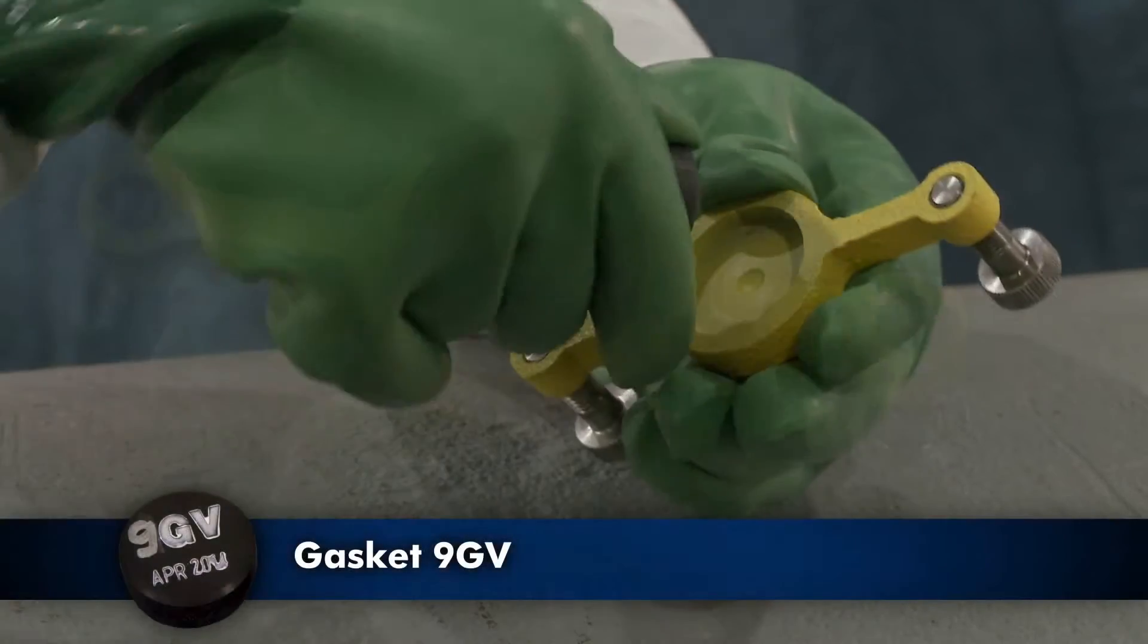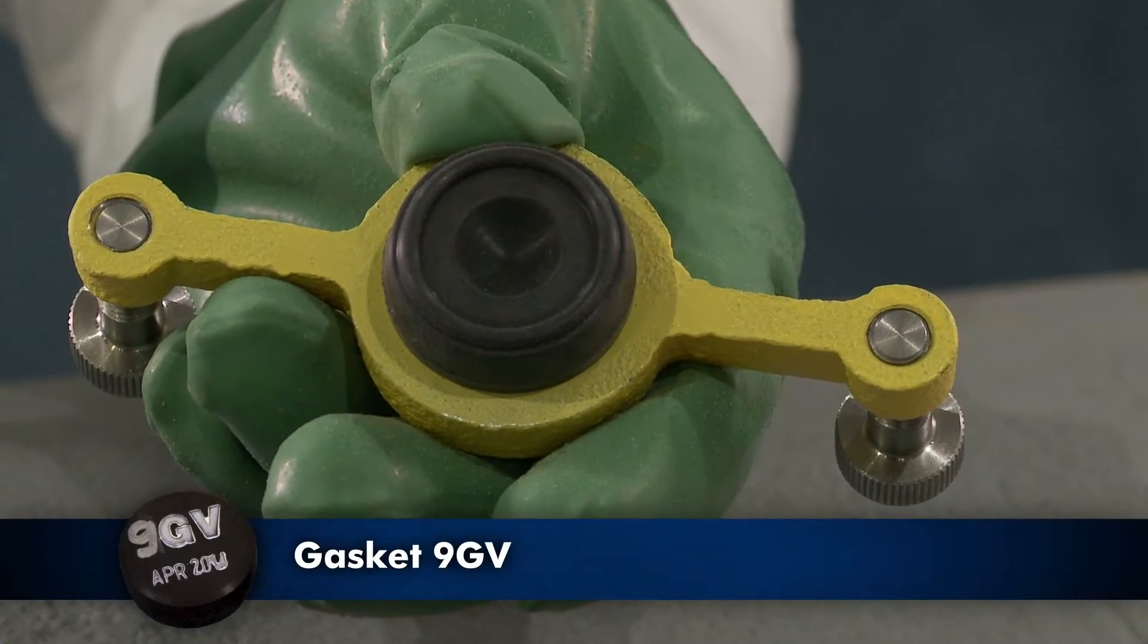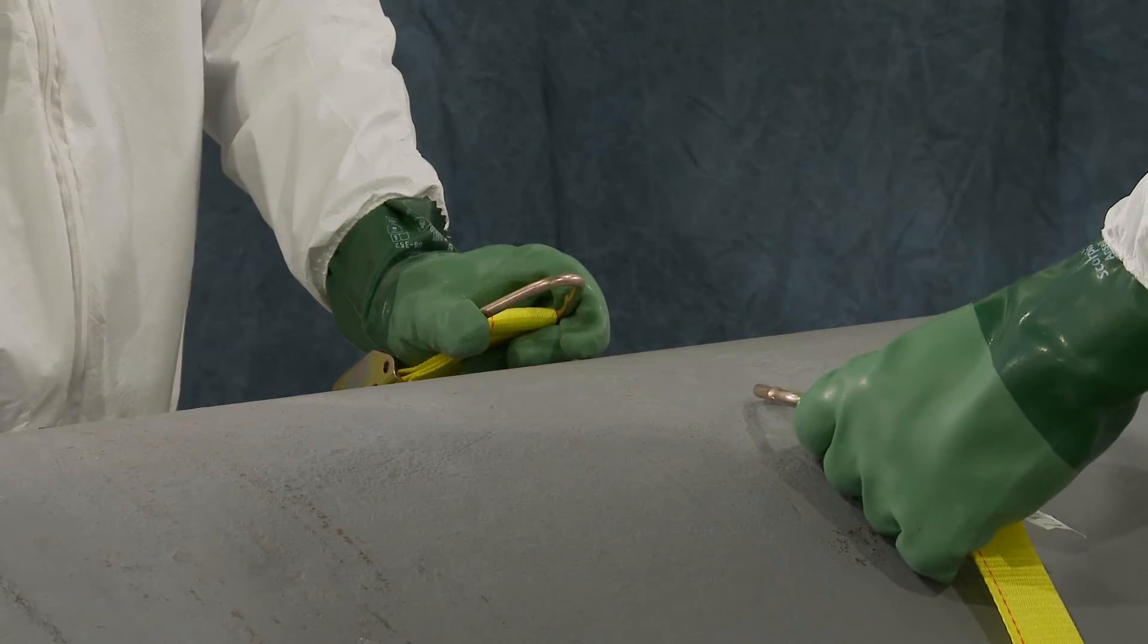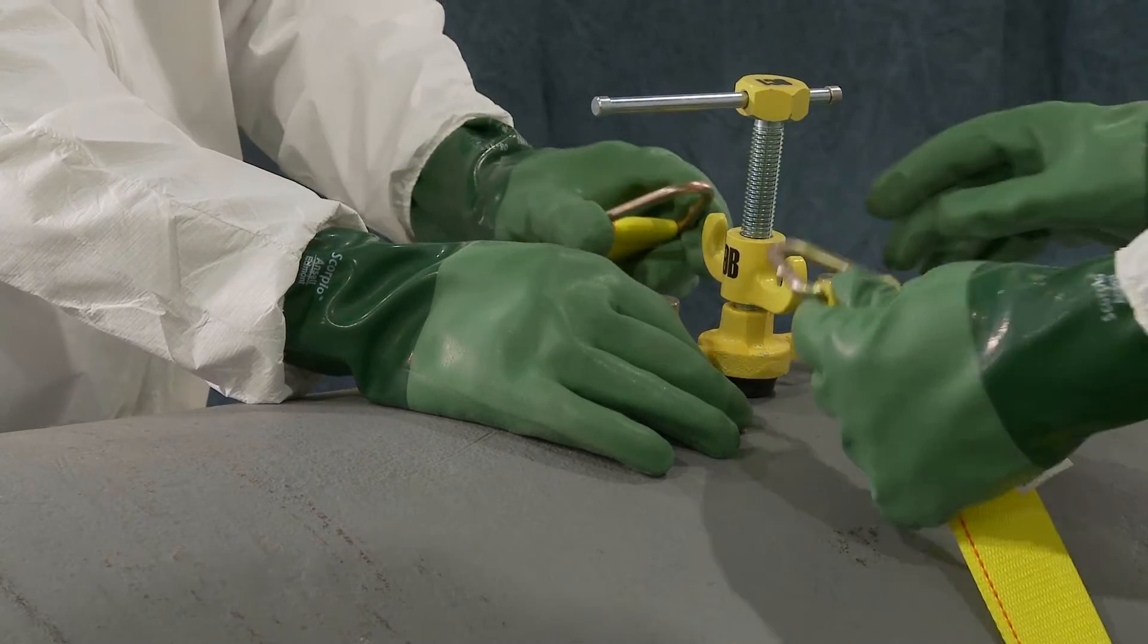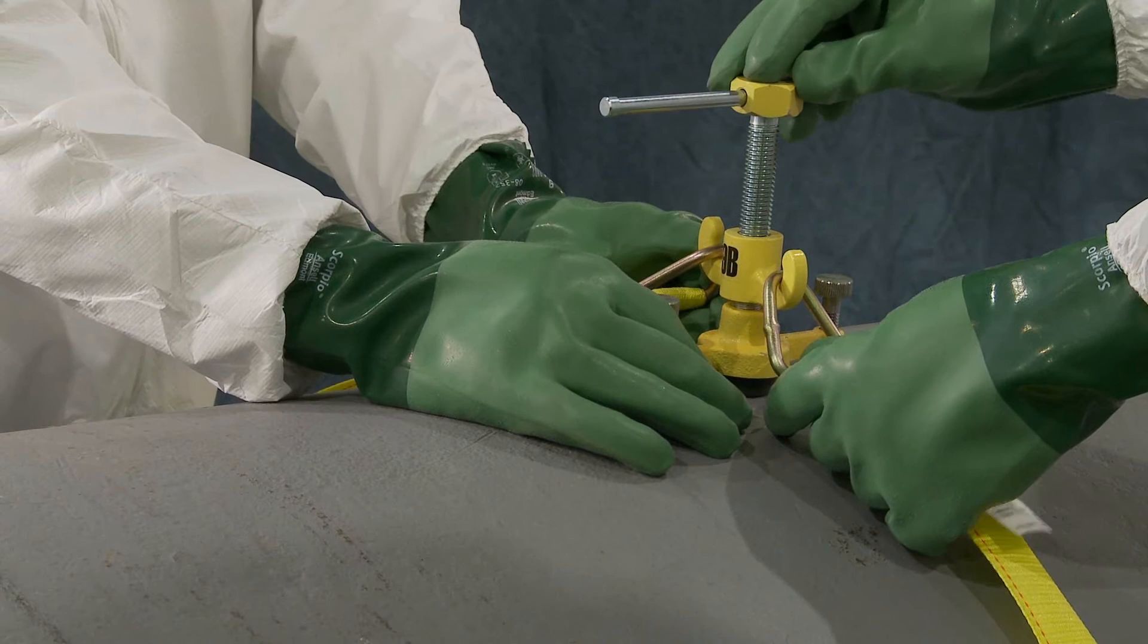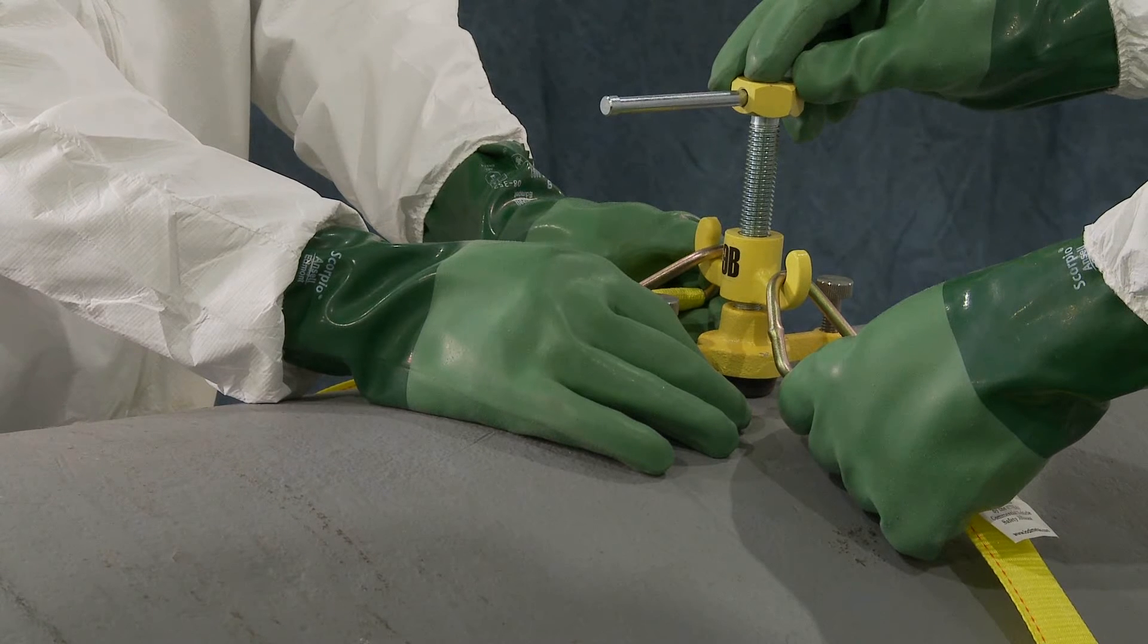Position the gasket 9GV inside the patch and set it to the side of the leak. Center the yoke and cap screw into the depression on the top of the patch. Hook the strap to an ear on each side of the yoke. Keep the strap as short as possible.